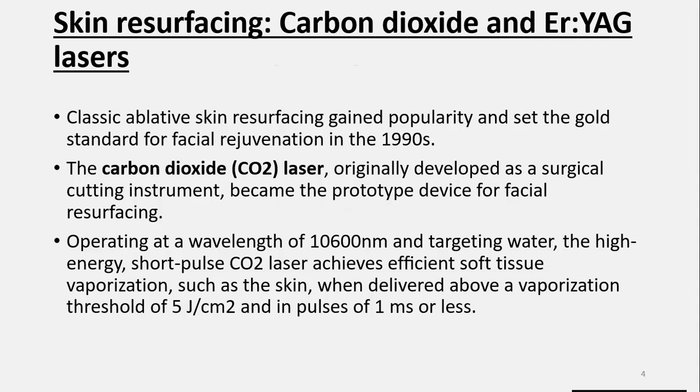The CO2 laser operates at a wavelength of 10,600 nanometers and targets water. The high energy, short pulse CO2 laser achieves efficient soft tissue vaporization, such as skin, when delivered above the vaporization threshold of 5 joules per centimeter square and in pulses of 1 millisecond or less.